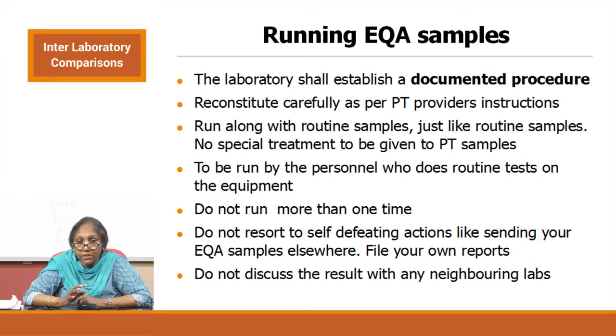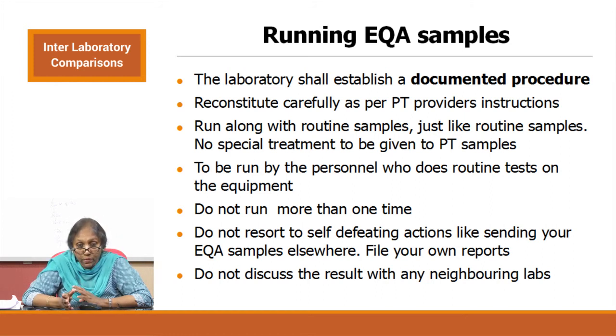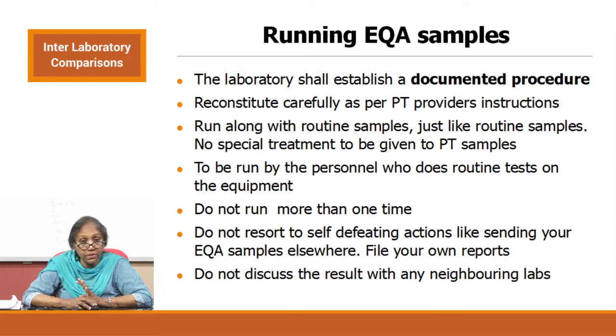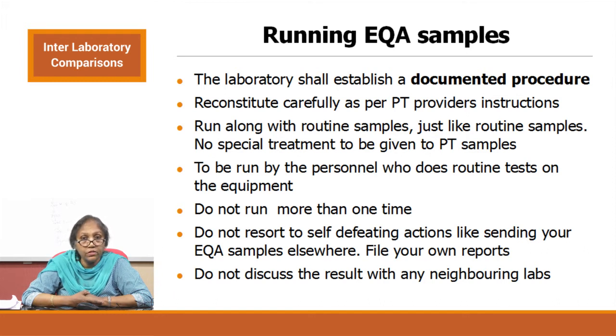The standard requires that the laboratory establish a documented procedure for running EQAS samples. Reconstitute the samples carefully as per the PT provider's instructions if they come in lyophilized form. Run them along with routine samples — no special treatment is to be given to PT samples. There are many self-defeating mechanisms people employ. The primary purpose is to understand if there are any instabilities in your system, not just to produce a good-looking EQAS report.